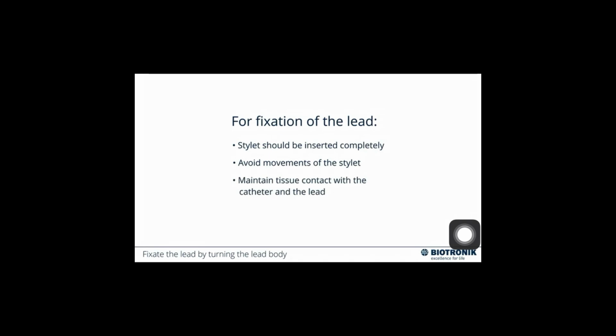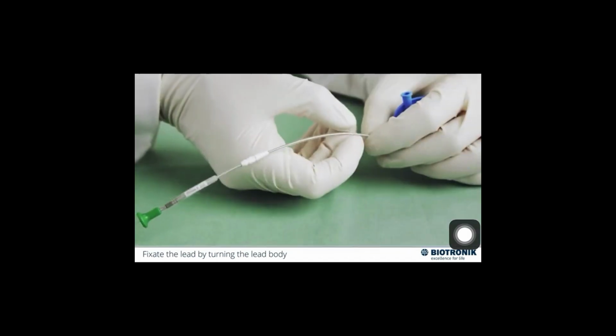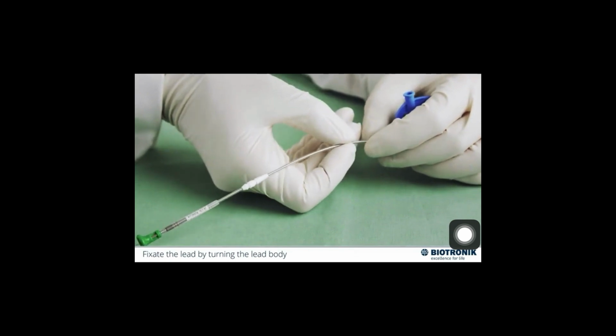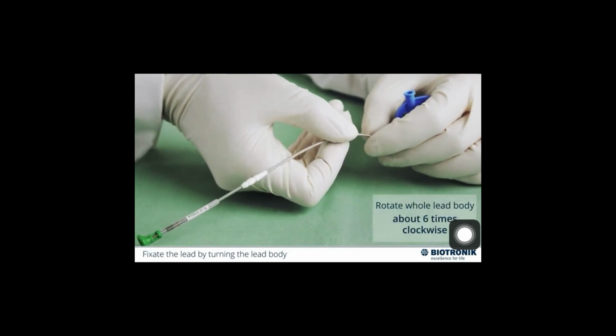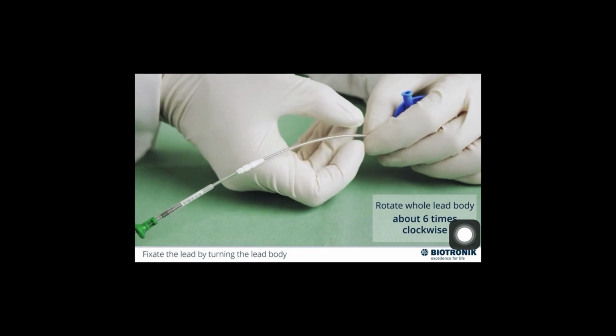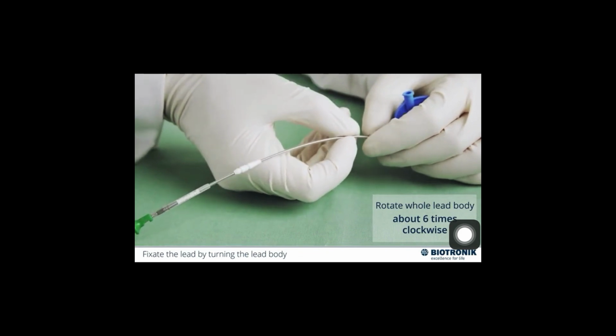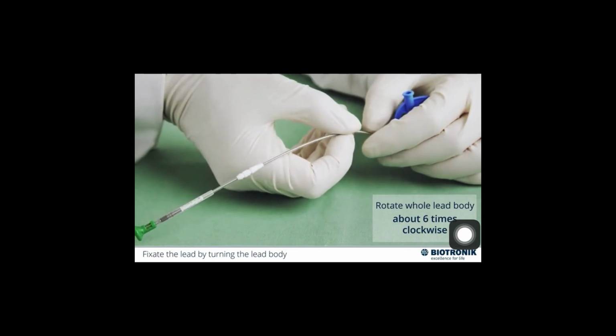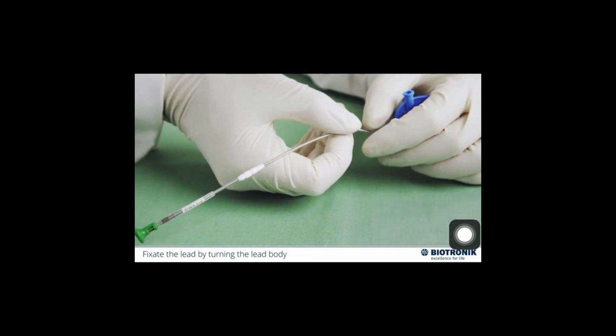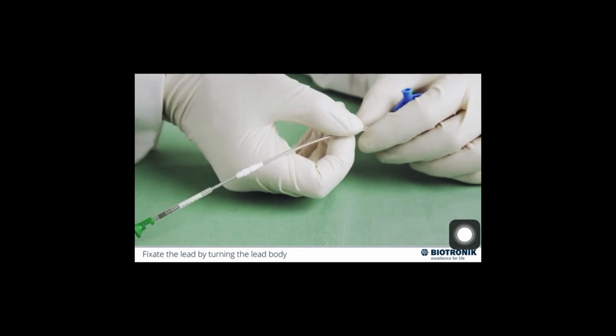Maintain close contact to the tissue with the delivery catheter as well as with the lead before fixating the lead. Push the lead slightly against the tissue, however, avoid excessive pressure when using the stylet. Fixate the lead at the target area by turning the whole lead body completely about 6 times clockwise. Grip and turn the lead body at the catheter end. Turn the lead slowly, and after each rotation make pauses of around 10 seconds to ensure the torque transmission.